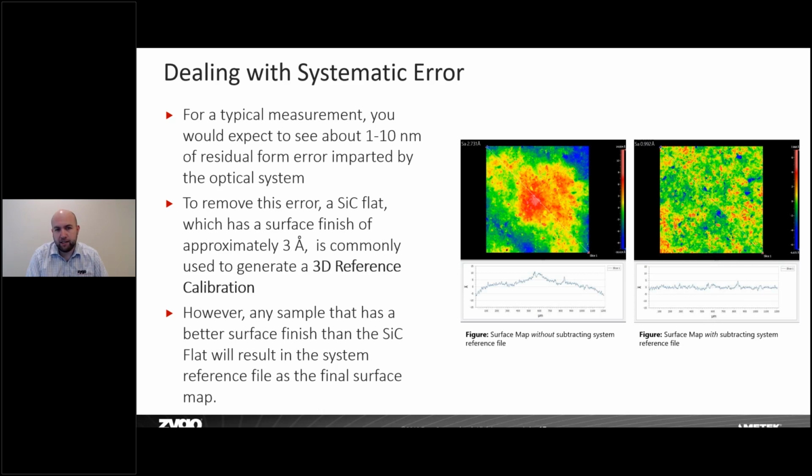However, you can use any sample that's significantly smooth and flat enough. Less than 3 angstroms generally is something that would be pretty good to use for a system reference file.